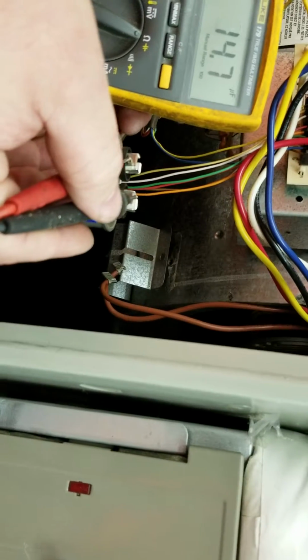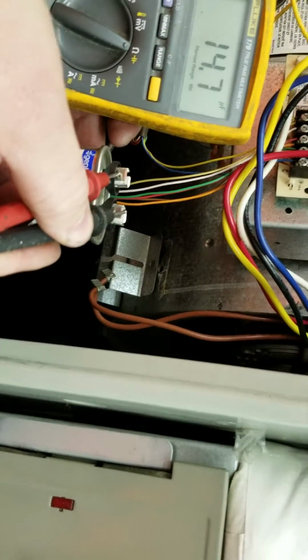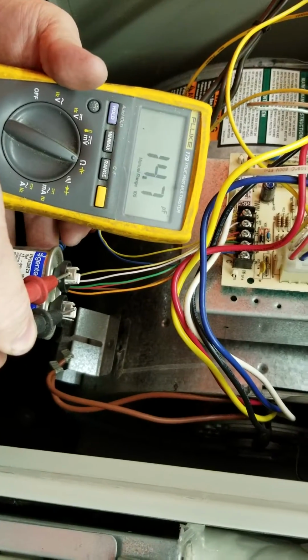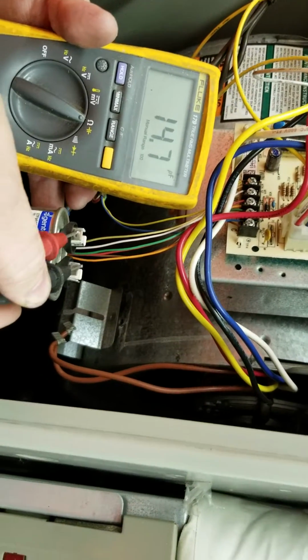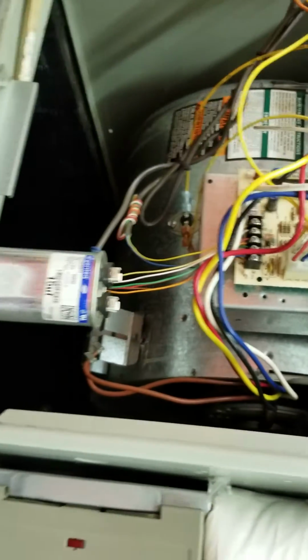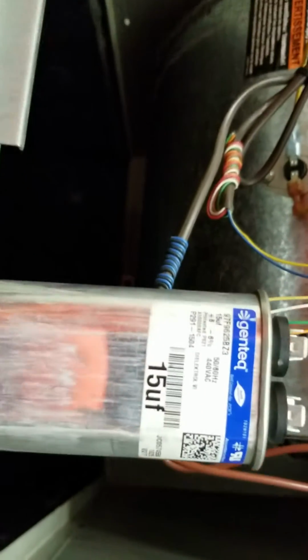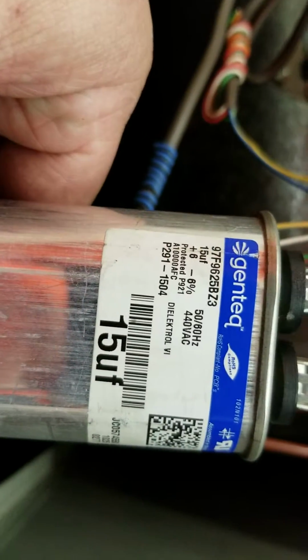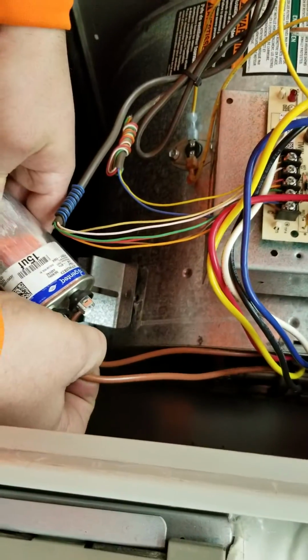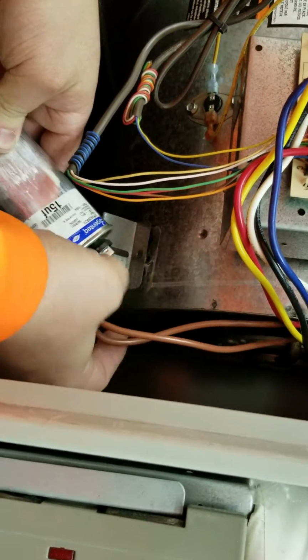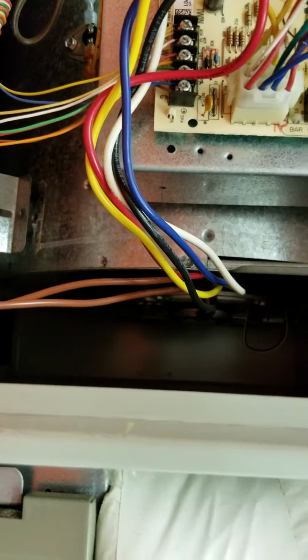Okay, one lead on each terminal. Okay, this one reads 14.7 microfarads. It is good. It's within the 6% tolerance. The tolerance will usually be found right on the label for the capacitor itself, along with other information about it. If you're outside of that 6% plus or minus, you are going to want to replace it. And then go ahead and reconnect your two wires.